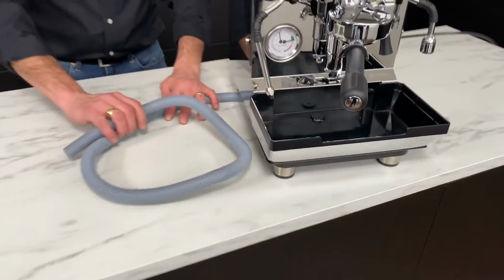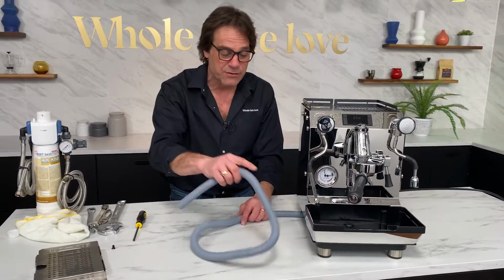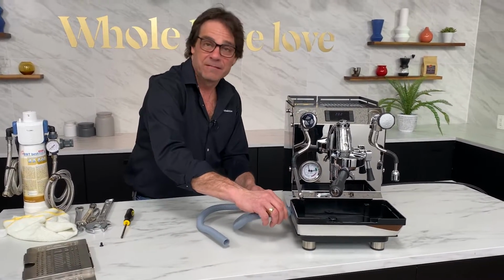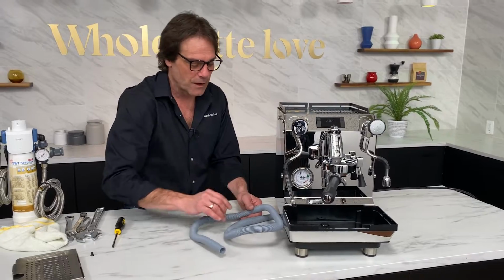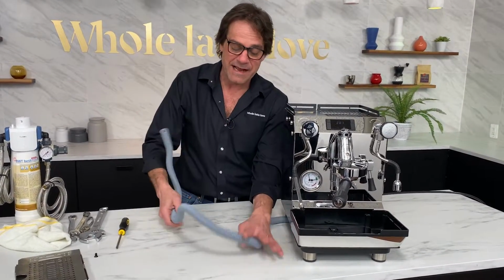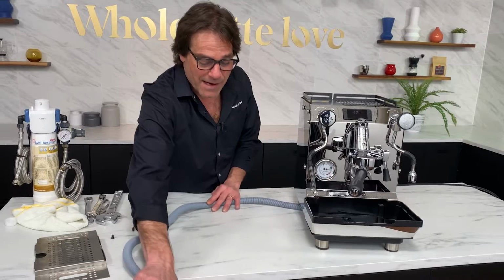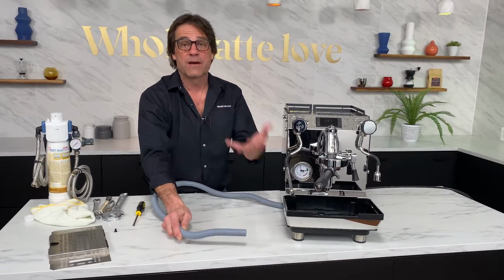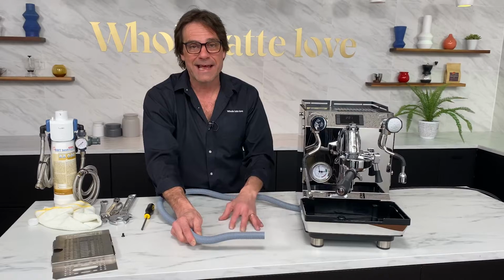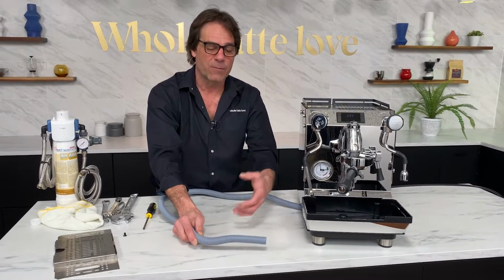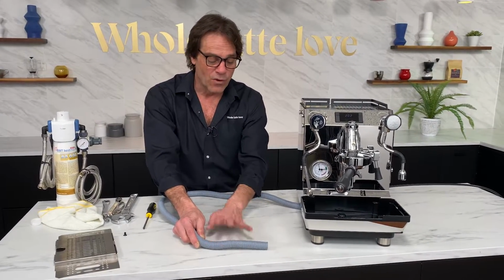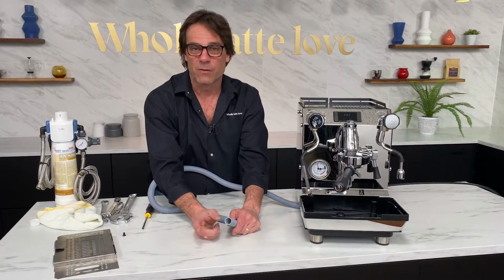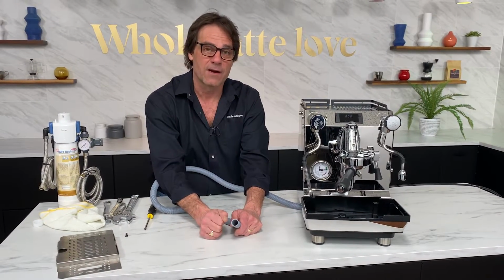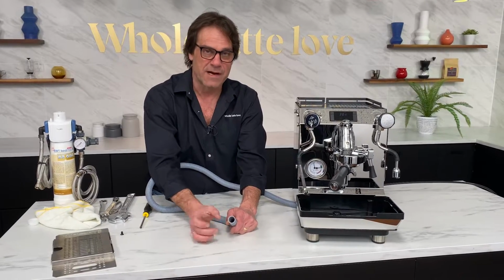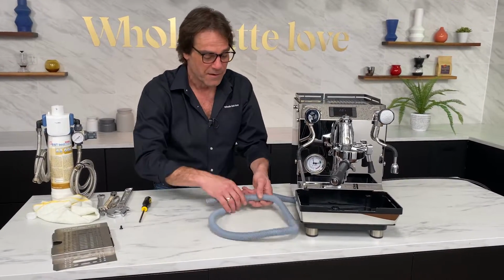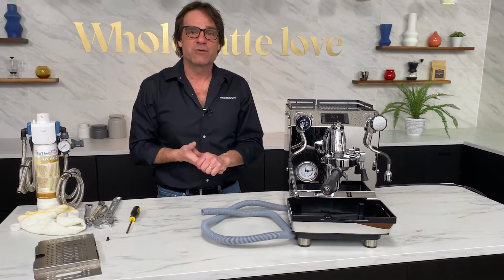Very important with this drain line: keep it below the level of the drip tray. If you've got a kink in it that's higher up, it won't drain, and your tray could overflow, so keep it below that level. You could flop this into a sink if you wanted, but the real way to do it permanently is to use what we call a stand pipe—a pipe open to outside air pressure so it can drain properly. Don't hook it up like one of those inlets for a dishwasher or garbage disposal; it won't drain. It has to be open to outside air pressure. So it's pretty easy to hook up to a drain line.